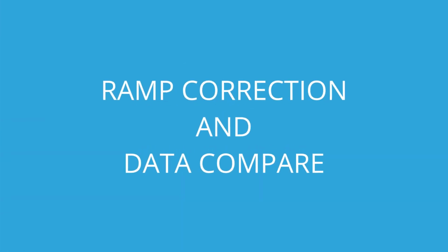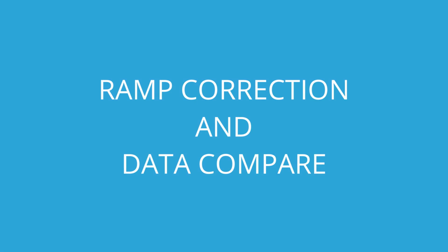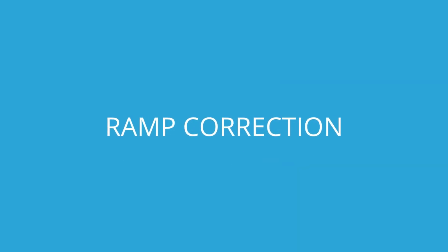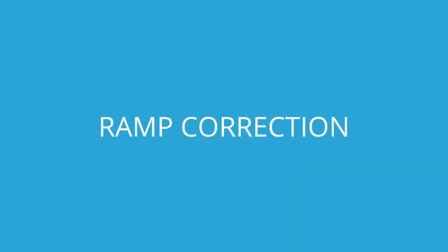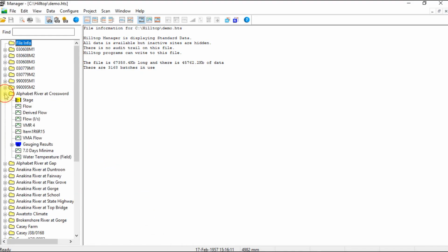In the third and final episode of Editing Data in Manager, I cover two specific operations, ramp correction and data compare. A ramp correction lets you correct the data for systematic errors. You can correct for errors in the data logger's clock and for drift in the instrument. It works by adjusting the recorder's values to match the check values.